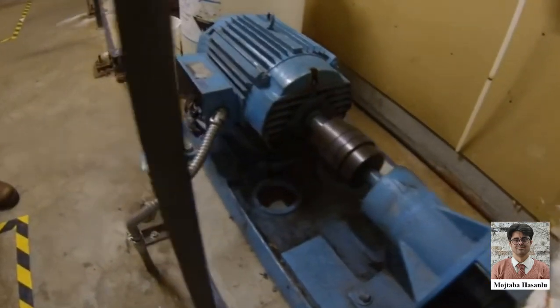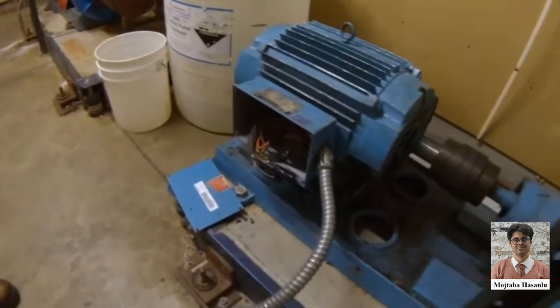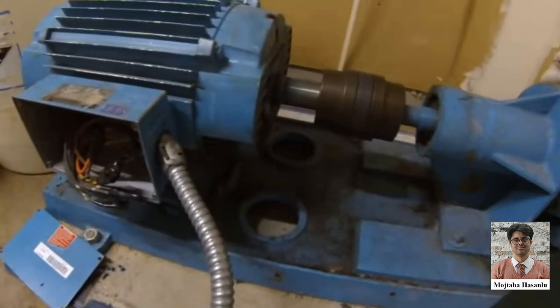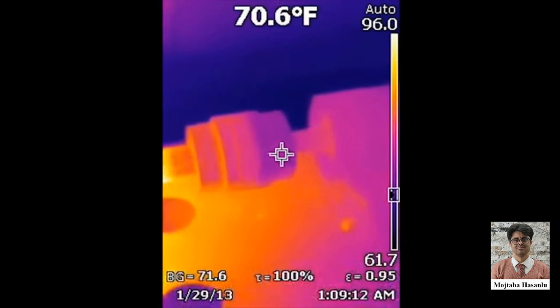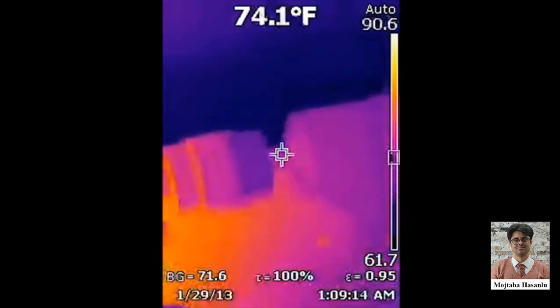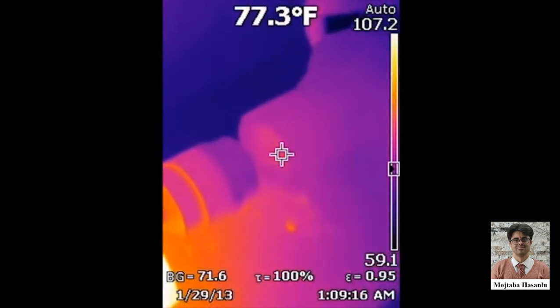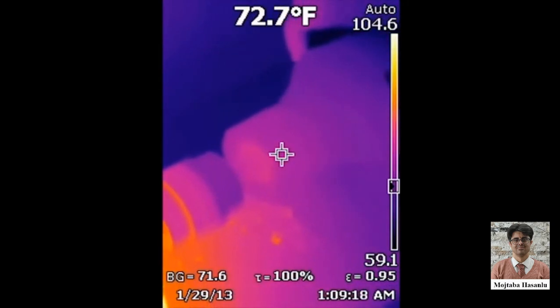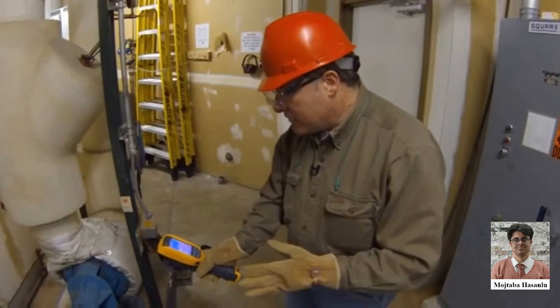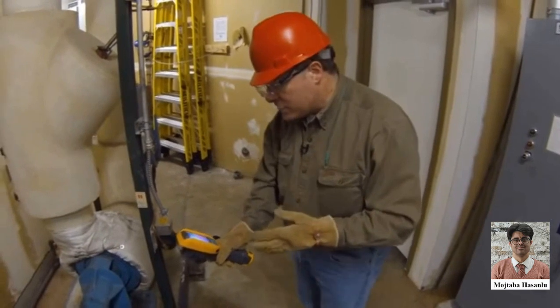All right, you have to be a little bit careful when you're taking a look at couplings and shafts and things like that, because they tend to be a shinier metal, a lower emissivity material. So sometimes you can get reflections off of them that aren't really there and aren't indicative of the actual heat. In this case, I'm not seeing too much going on.